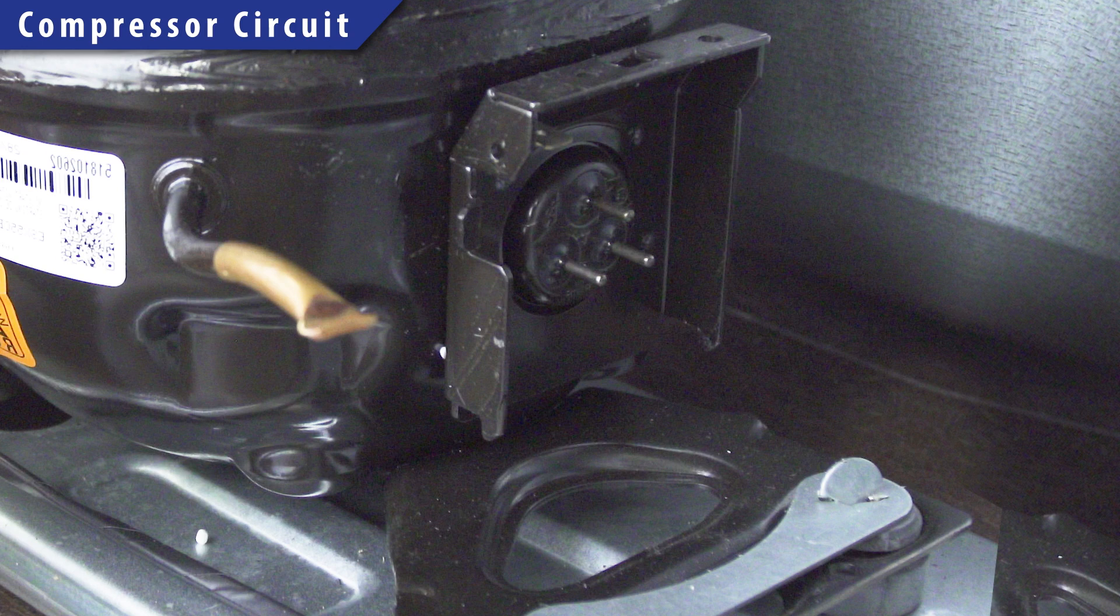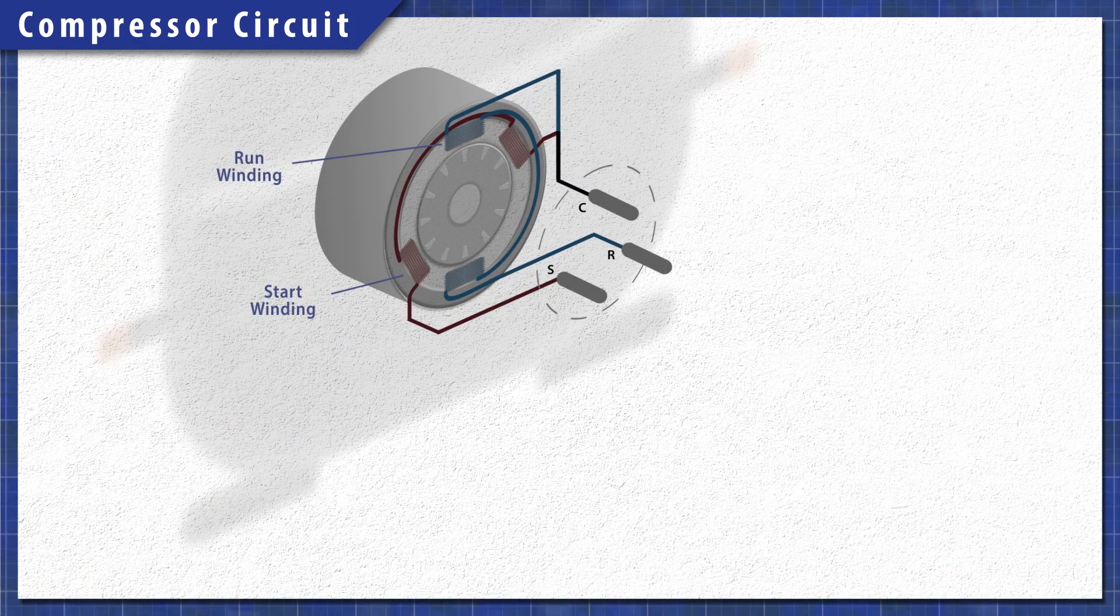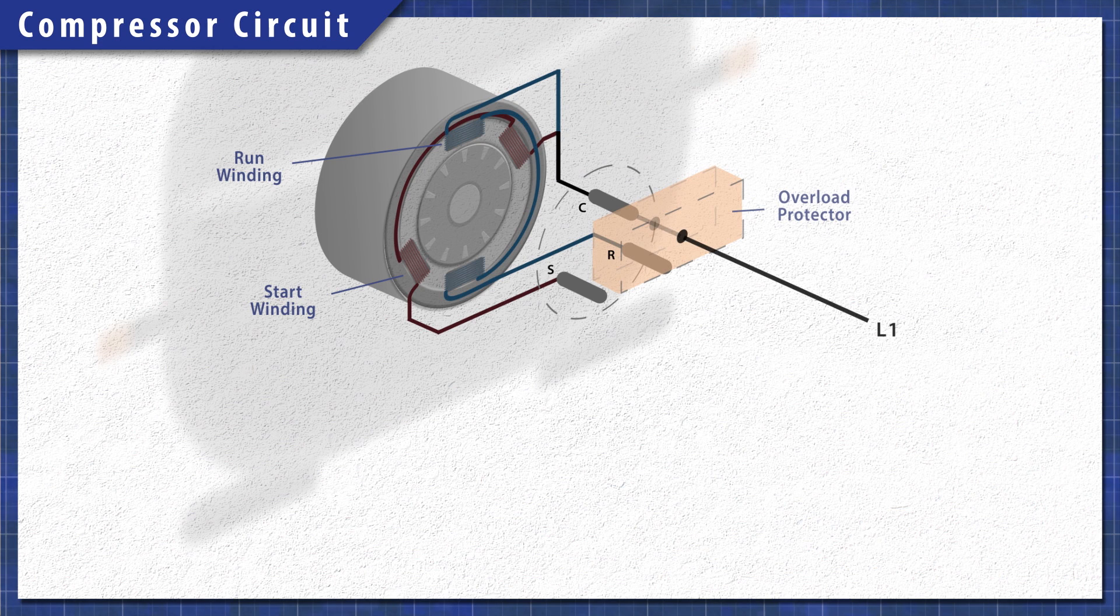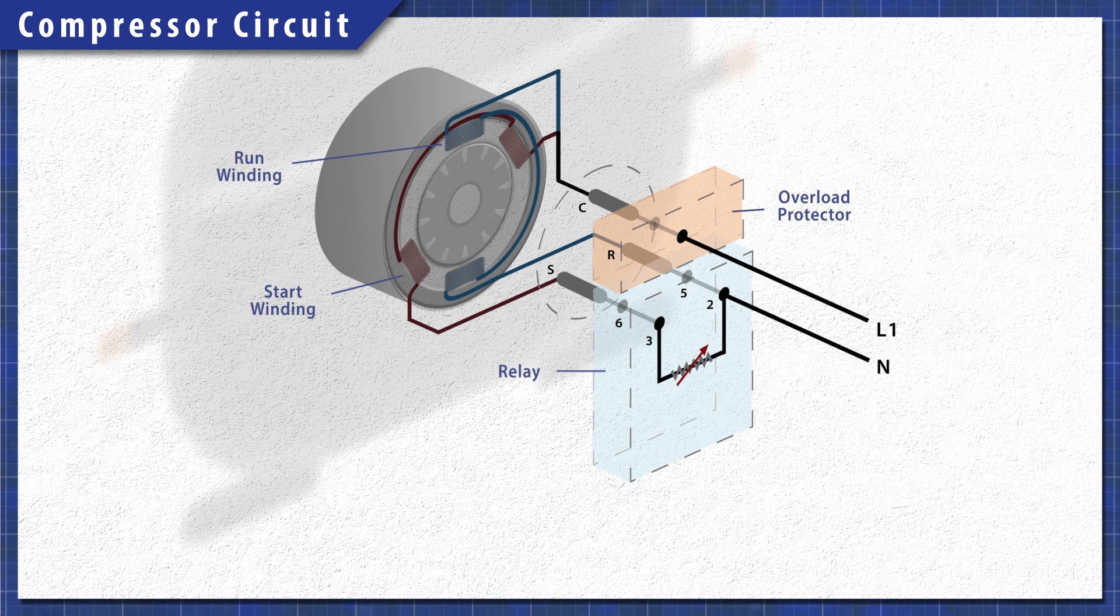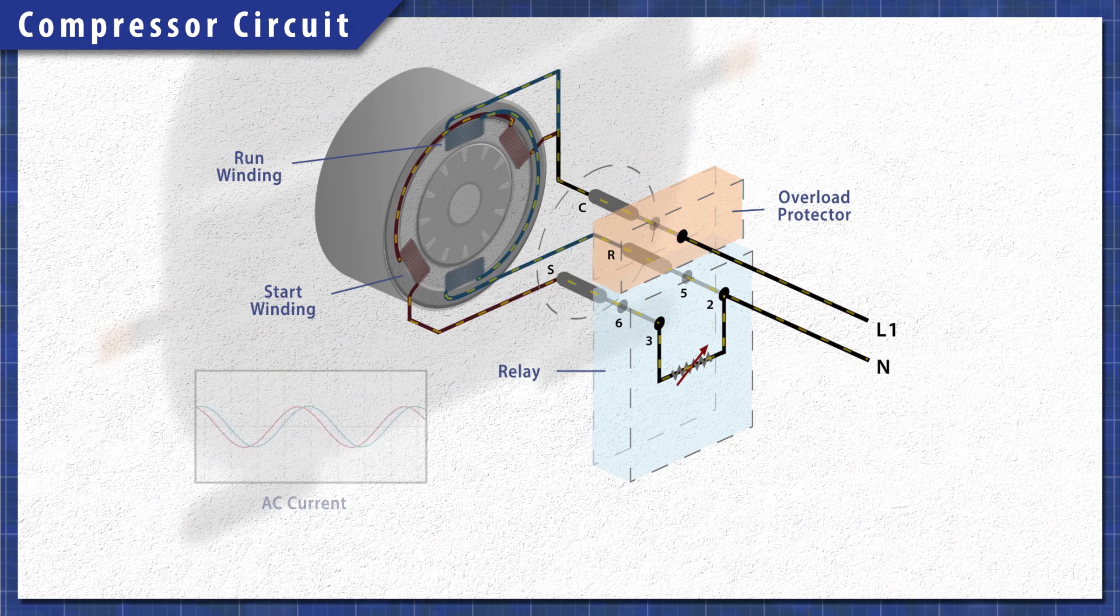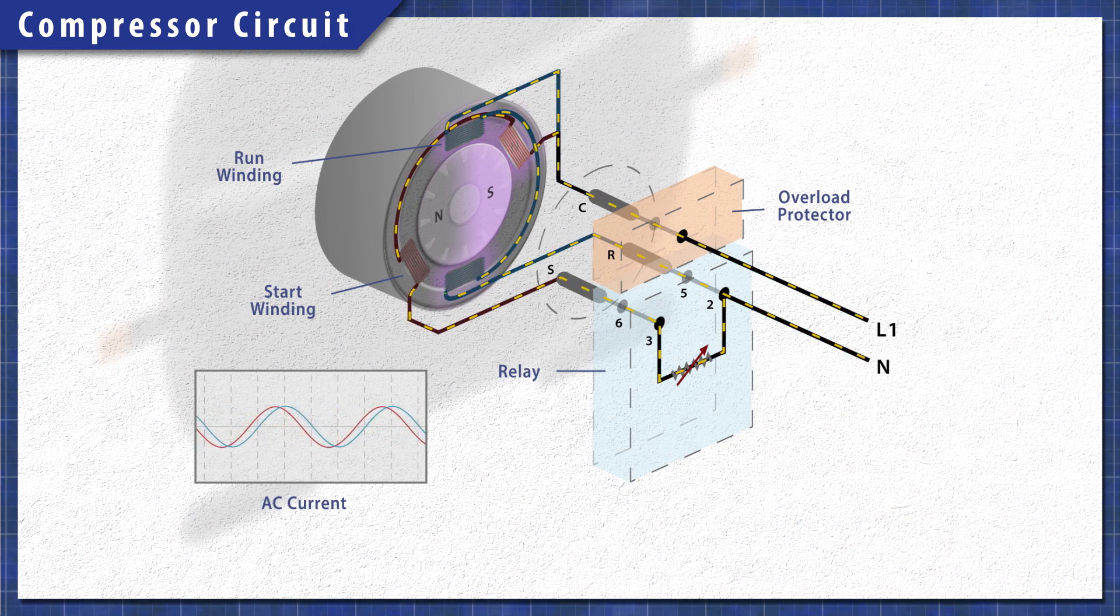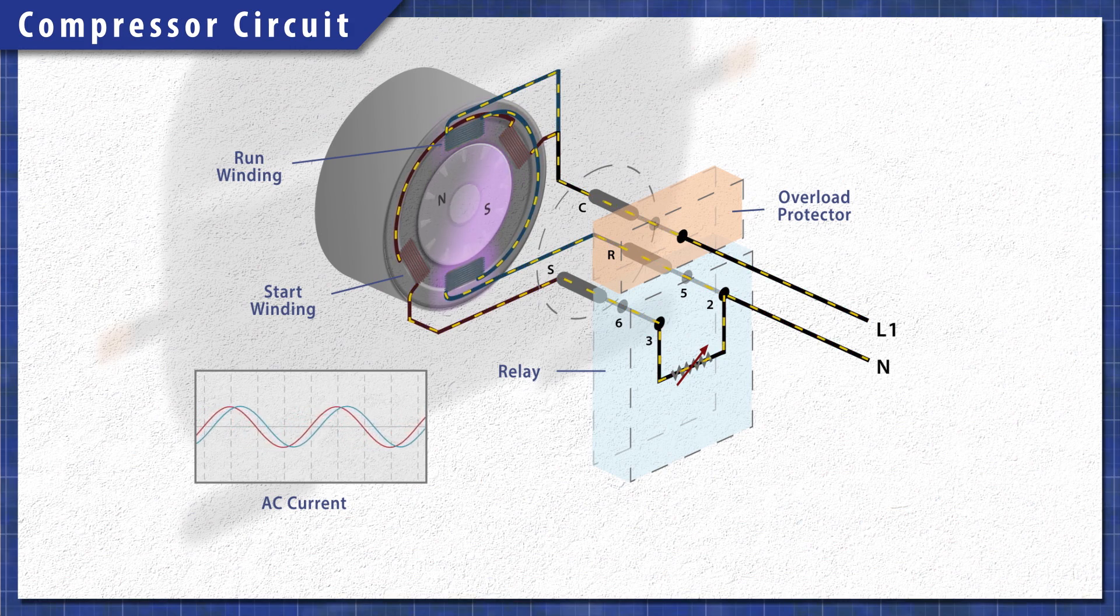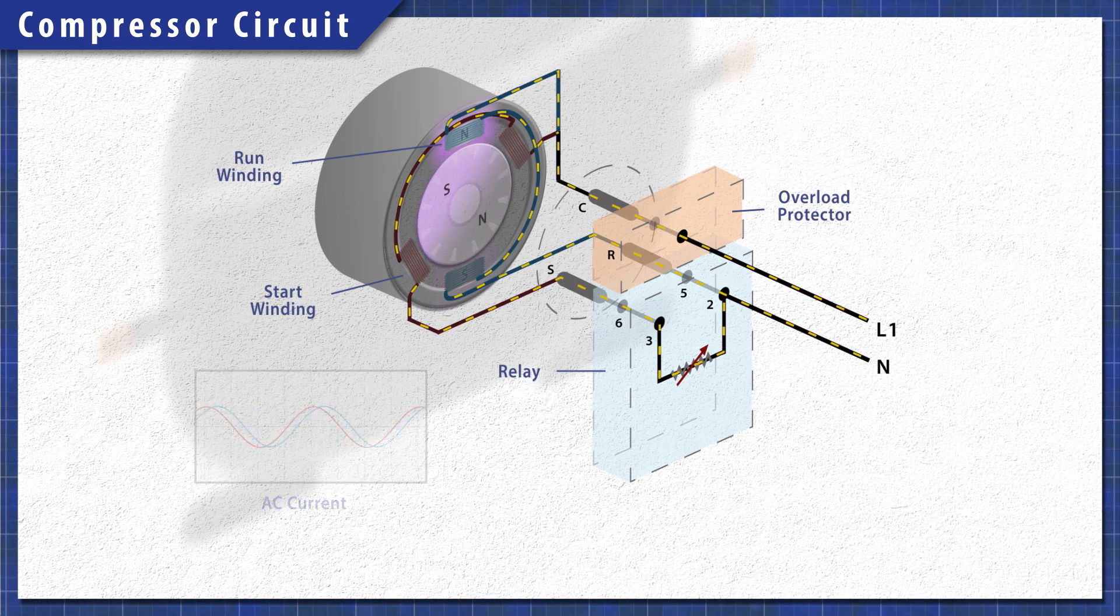The compressor uses a single phase motor. It has a start winding and a run winding which are both connected to a common terminal. Attached is an overload protector that disconnects power if the current or temperature gets too high. Single phase motors use resistance or a capacitor to create a phase shift in the start winding. This rotating magnetic field creates the torque needed to start the motor.